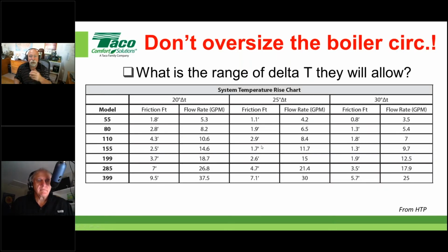Now I'm going to go through this really fast because I have several manufacturers here. Again, I'm not stepping on anybody's toes, and I'm not trying to purposely leave anybody out. This is how to go through the boiler manufacturer's information and make sure you're sizing the pump more correctly. What I'm generally saying is take this circulator out to the extreme that the boiler manufacturer has shown you in writing that you can do.